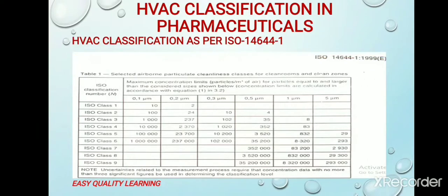This is the ISO 14644-1 classification. ISO 1 to ISO 9 classes are given; in pharmaceuticals we use classes 5 to 8. Class 5 is equivalent to Grade A, Class 6 is equivalent to Grade B, Class 7 is equivalent to Grade C, and Class 8 is equivalent to Grade D. The number of 0.5 micron and 5 micron particles is specified and is used for area classification as per Schedule M, European guidelines, and US FDA guidelines.